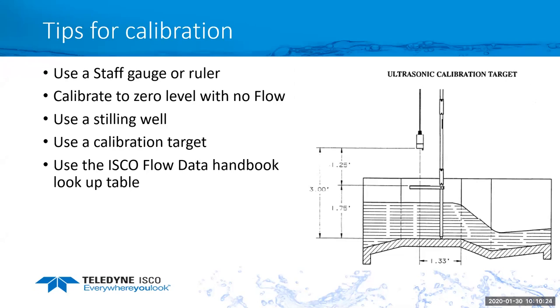Another good idea is to use the ISCO flow data handbook or the manufacturer's lookup table. With that, you would look at the height or depth, water depth, and then find out the associated flow rate, and your flow meter should match that.